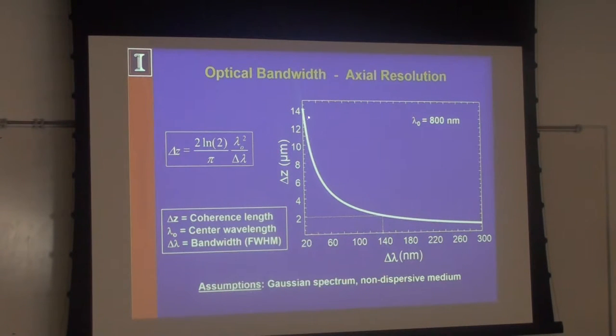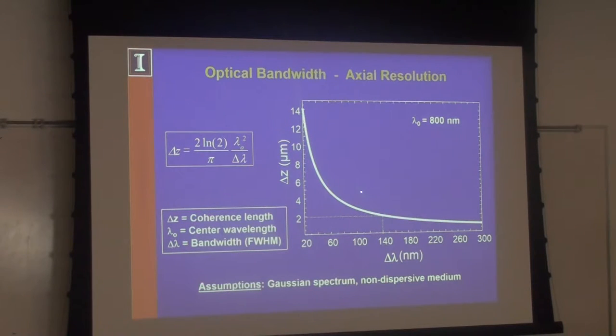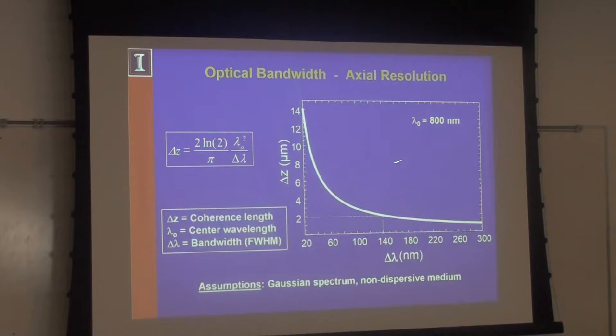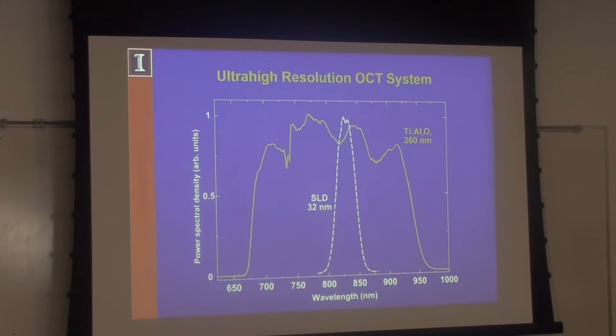The axial resolution in OCT is inversely proportional to the bandwidth: if you want a shorter coherence length and higher axial resolution, we need broader bandwidth, a larger Δλ. If we want to get down to 2 micron axial resolution we have to use quite unique optical sources with huge bandwidths, and that's hard to generate. Using longer wavelength light also makes resolution worse. These are trade-offs we always have to make.